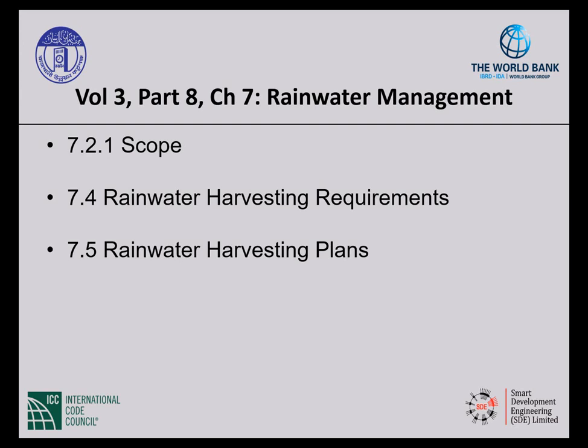So 7.2.1, the scope, says that the chapter specifies the general requirements for rainwater harvesting for different categories of the building according to their occupancy classification, together with the ancillary works of groundwater recharging, such as perforated pipe, pits, and inspection chambers. And 7.2.2 lets us know that it also covers the design, installation, and maintenance of elements for the rainwater drainage systems, and everything around it, how it connects to the building sewer, and so on. And then it lets us know that the stormwater drainage on the ground is not covered in this code. We're just talking about stormwater drainage of the building when we talk about the rainwater management plan. So let's jump to 7.4 and 7.5 to talk about the requirements and the plan.